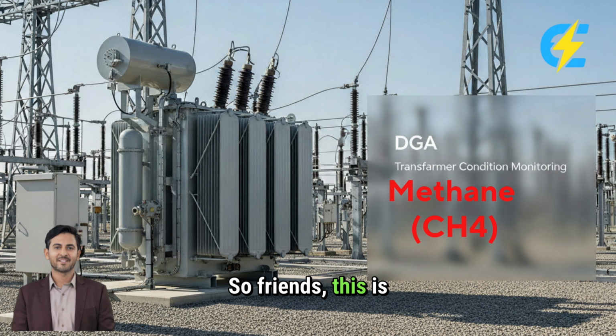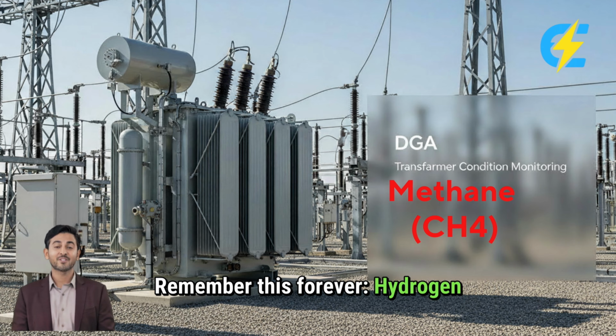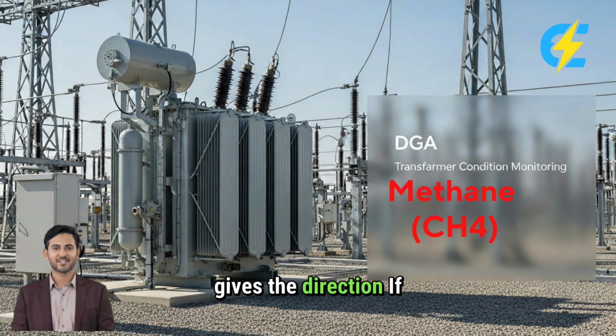So friends, this is the real meaning of methane in DGA. Methane does not scream. Methane explains. It tells you oil heating has started. Energy levels are increasing. And insulation stress is slowly evolving. Remember this forever. Hydrogen asks the question, methane gives the direction. If you track methane correctly, you don't wait for ethylene or acetylene to appear. You act early, you plan maintenance, and you save the transformer.